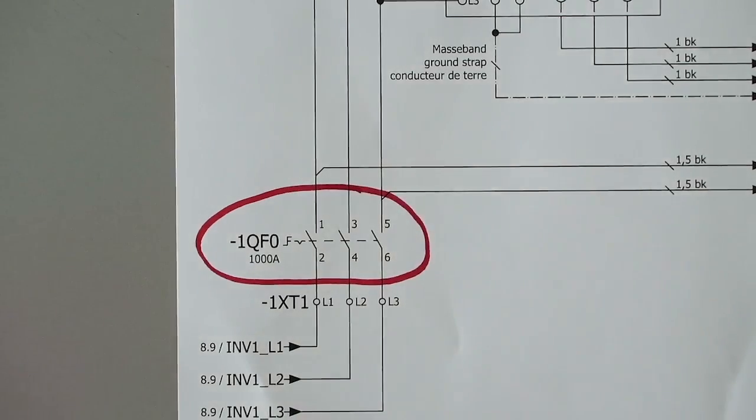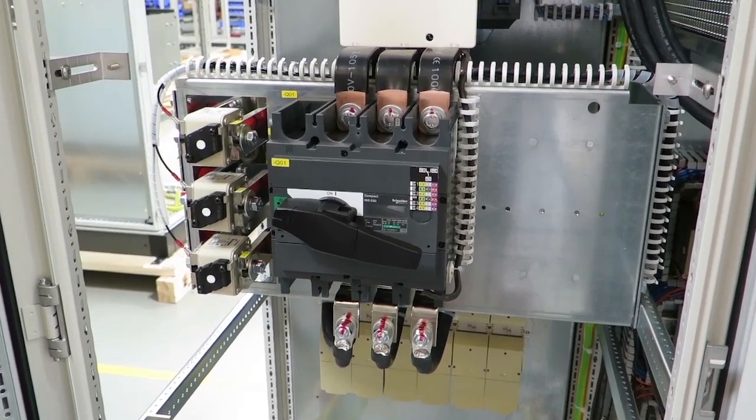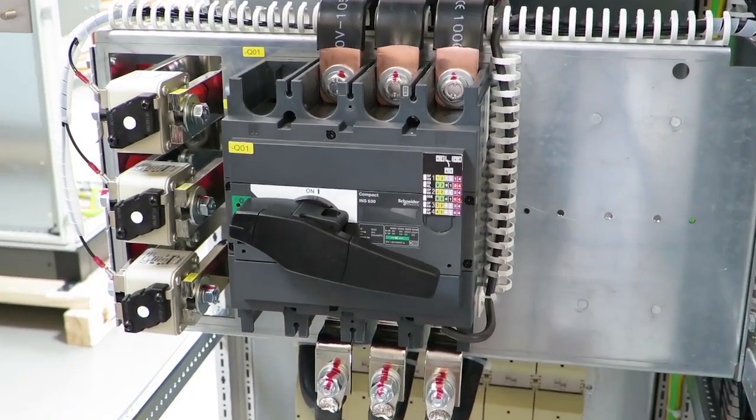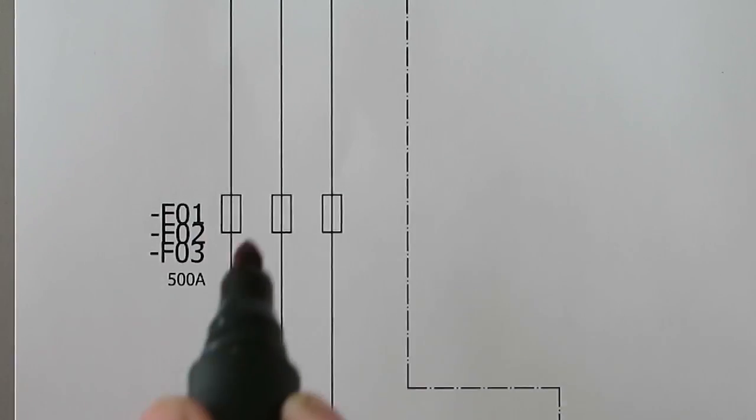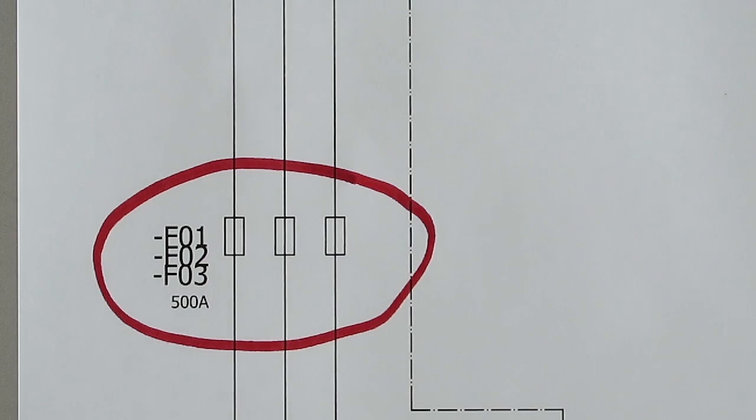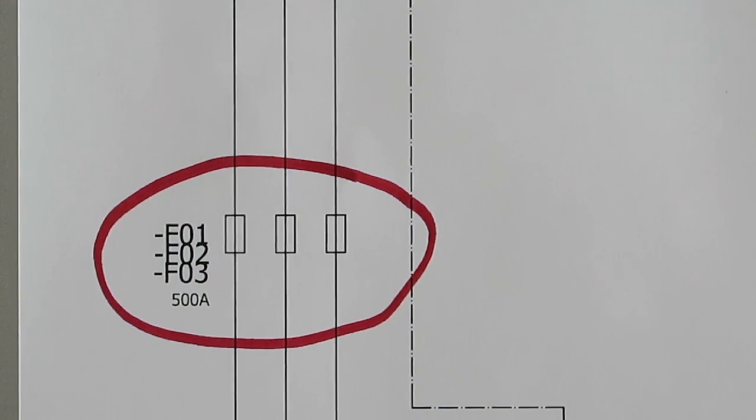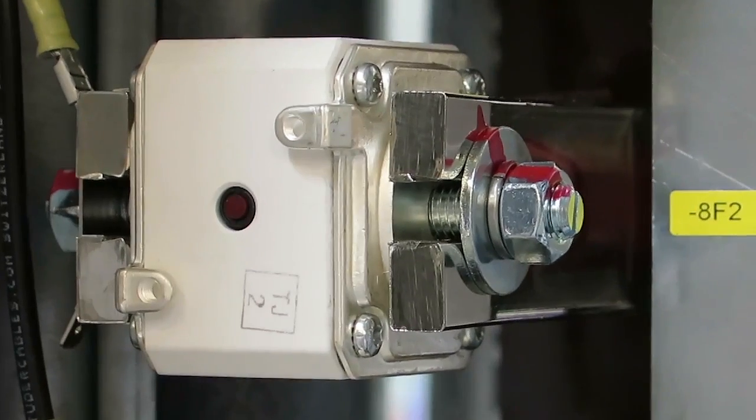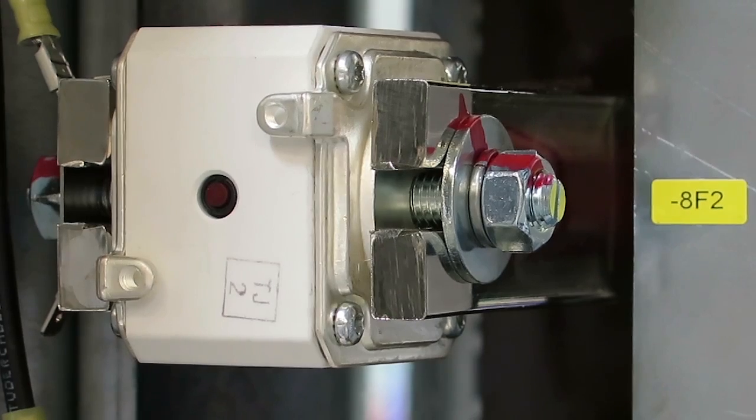A typical drive system is equipped with a main switch and is manually operated with a door handle. Superfast fuses on the input interrupt the power supply from the drive in case of a fault on the rectifier or within the DC link, and therefore make the damage as small as possible.